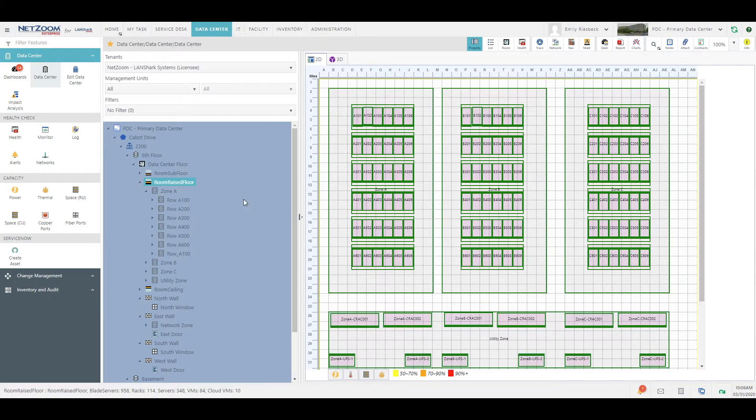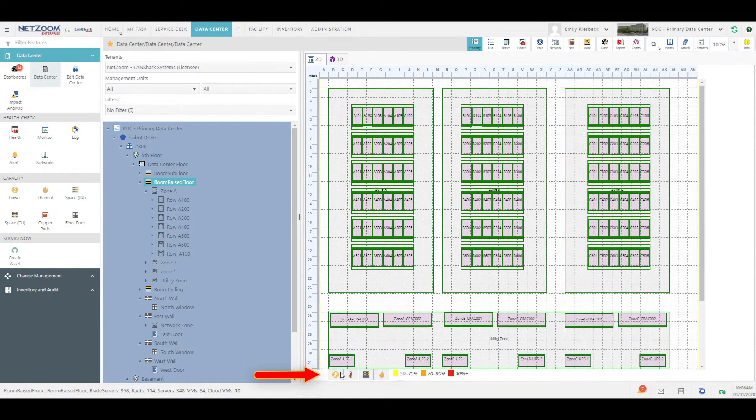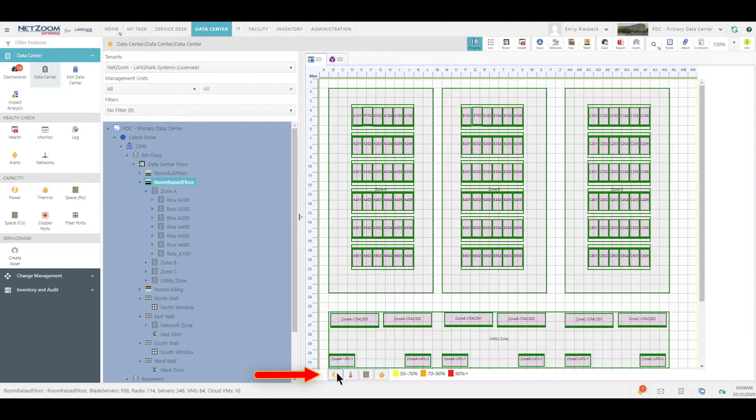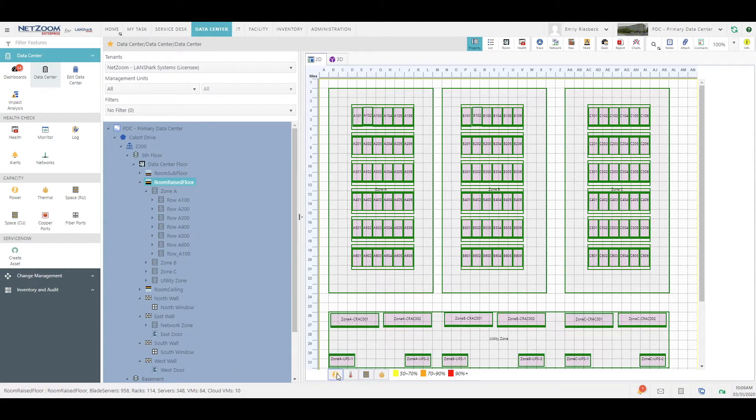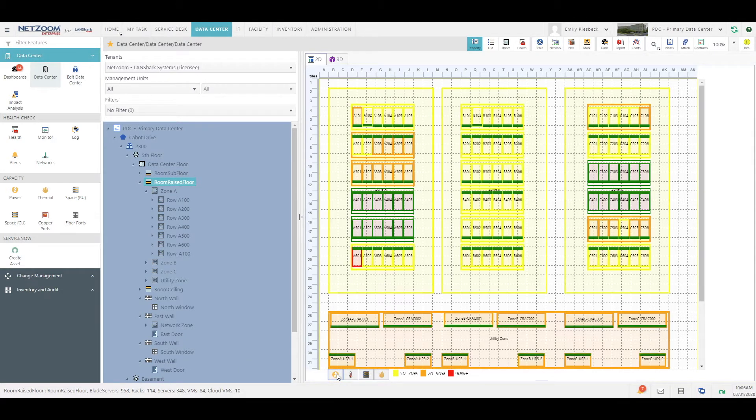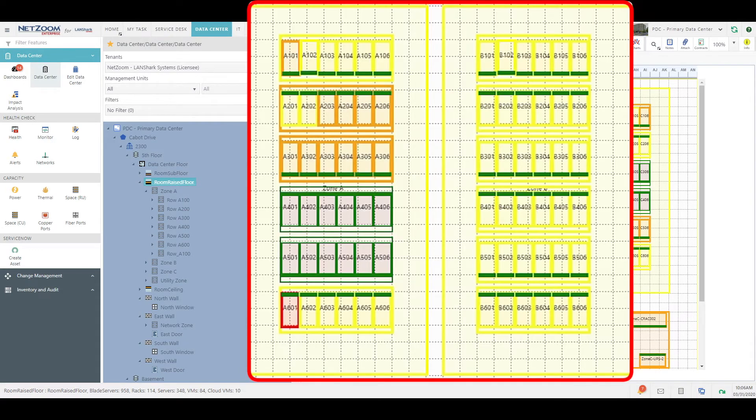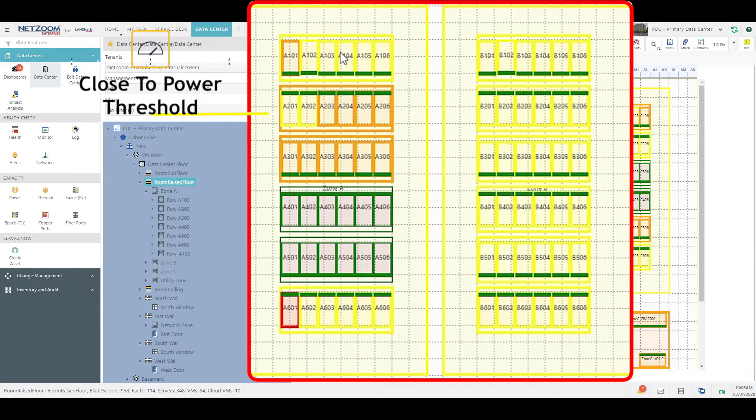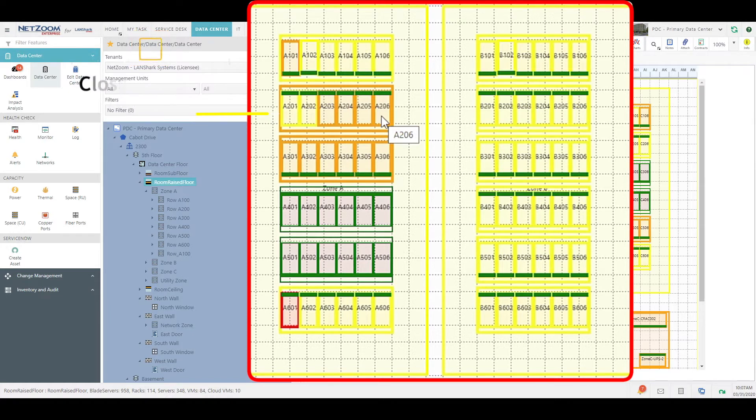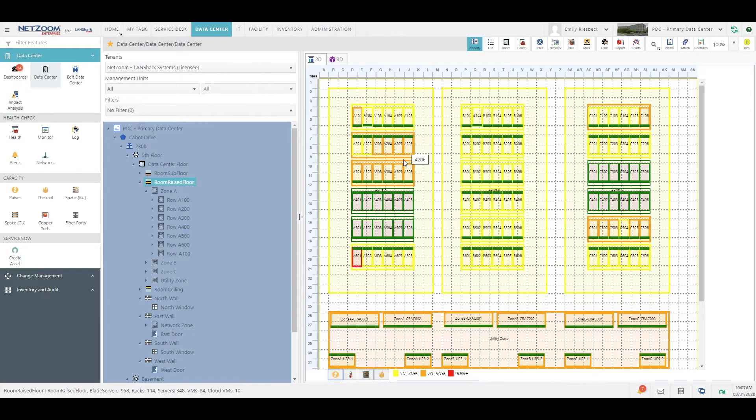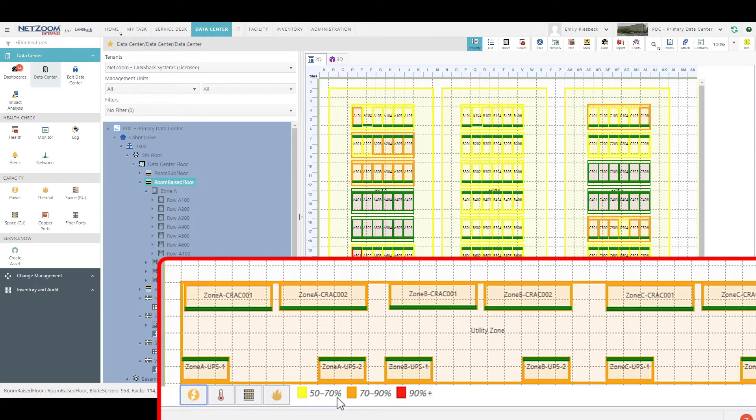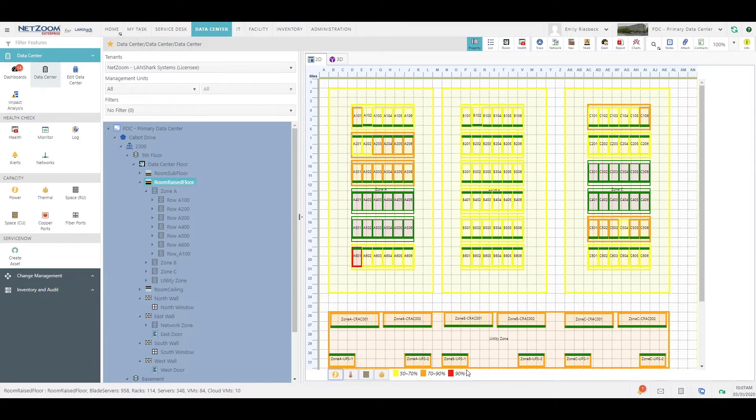If we select the room raised floor and click the power button, show power, we will see that each rack and row is highlighted based on power consumption. The darker yellow and orange colors are closer to the power threshold for those racks, rows, and zones. You can see the legend for the colors down here at the bottom of the pane.